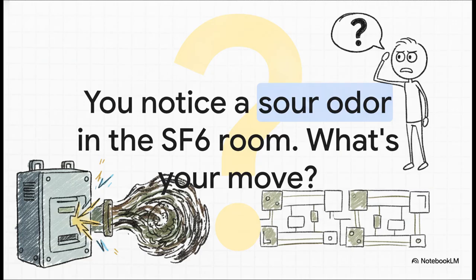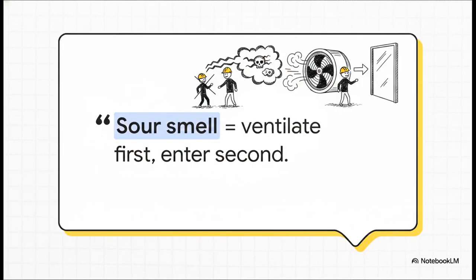Okay, let's put you in the hot seat for a second. Quick check for you. You open the SF6 breaker room right after a massive fault trip, and you immediately catch a sour, unusual smell. What is your very first move? Think about it. Your switchgear just interrupted a huge fault, and now the room smells wrong. Are you going to go in and inspect it? Stop right there. Here is the life-saving mandate you absolutely must remember. Sour smell equals ventilate first, enter second. Do not go in yet.